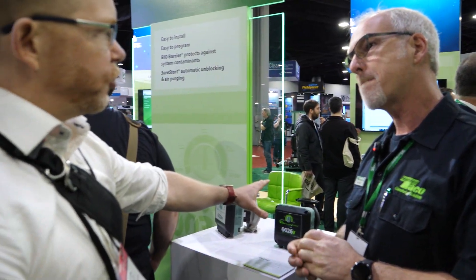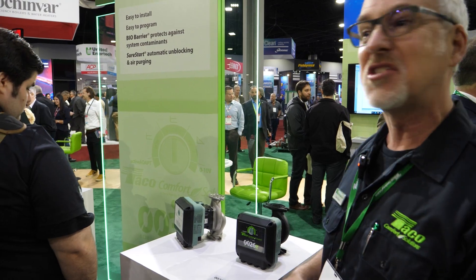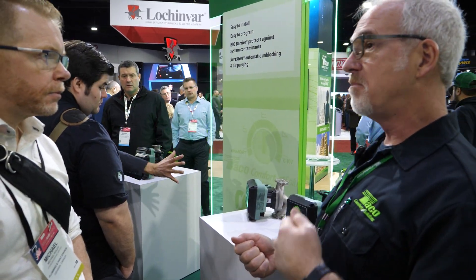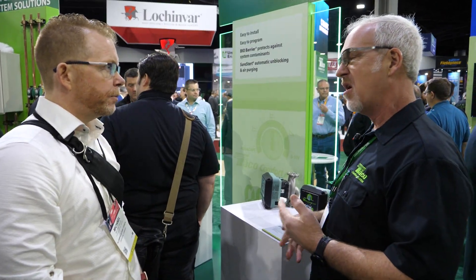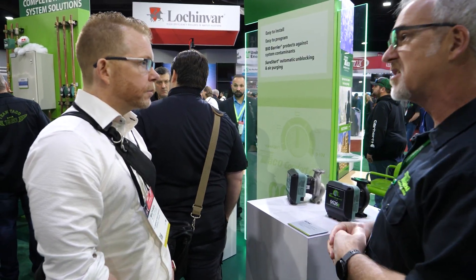Where do you see the dominant application for this circulator? By '26,' we're trying to state the foot of head that the product code means — so 0026 gives you 26 foot of head. The long number also tells you there's 50 GPM capable on that. I see these on snow melts, bigger geo jobs, domestic indirect water heaters — things where we need more volume. It's kind of a number two product in our Canadian marketplace.